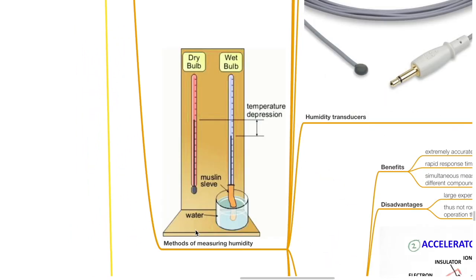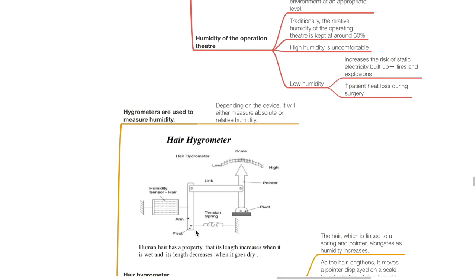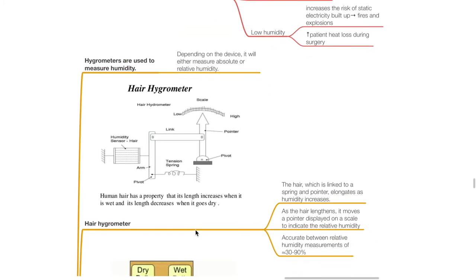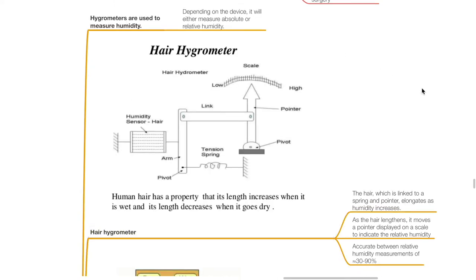Methods of measuring humidity. Hygrometers are used to measure humidity. Depending on the device, it will either measure absolute or relative humidity. The hair hygrometer: hair — either human or animal hair — which is linked to a spring and pointer, elongates as humidity increases, and this is displayed on a scale to indicate the relative humidity. It is accurate between relative humidity measurements of 30 to 90%.